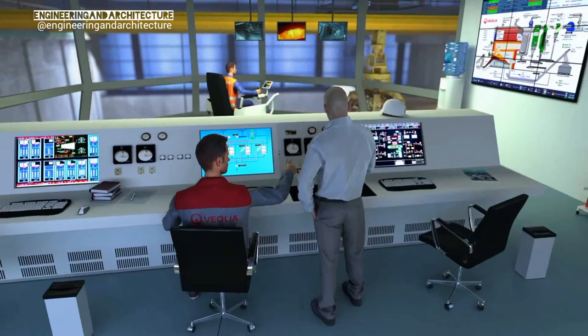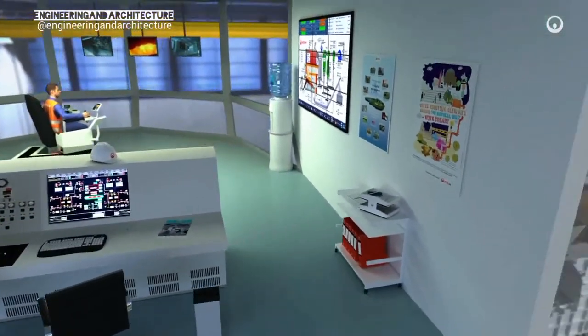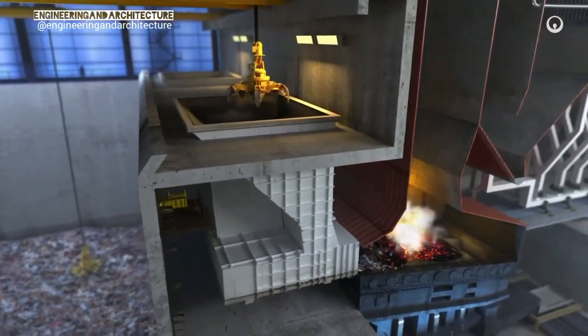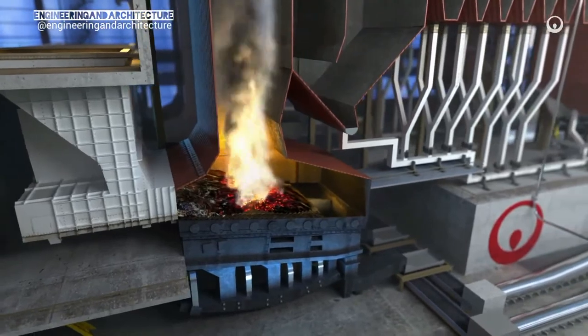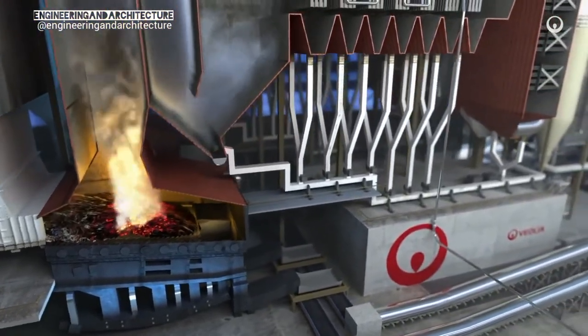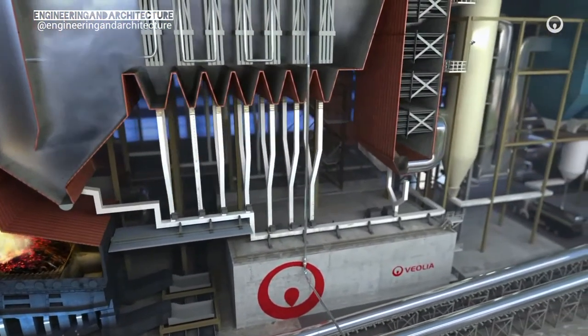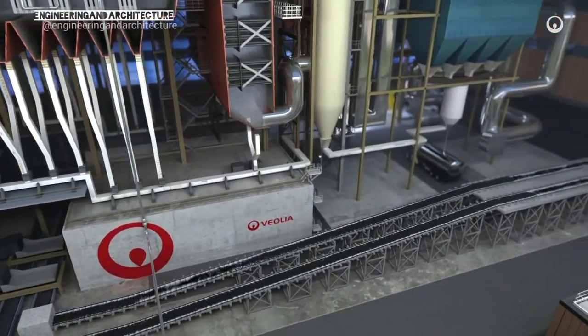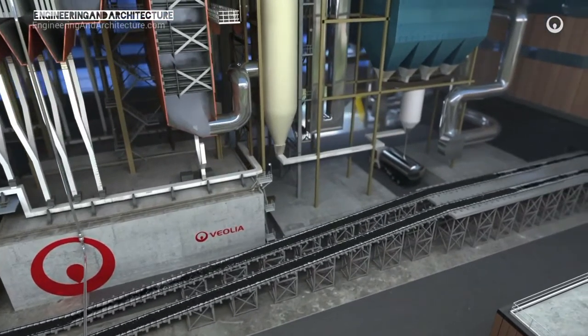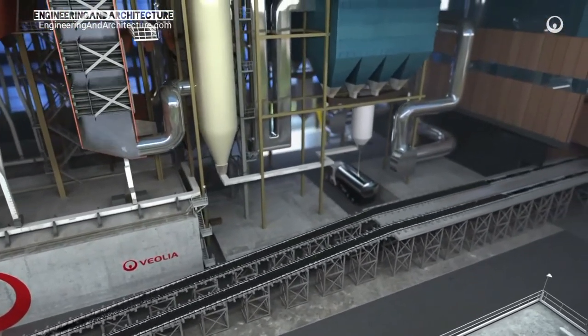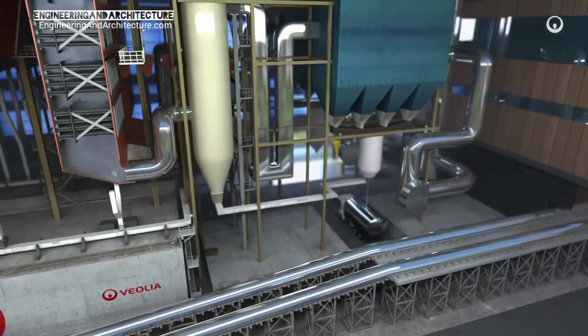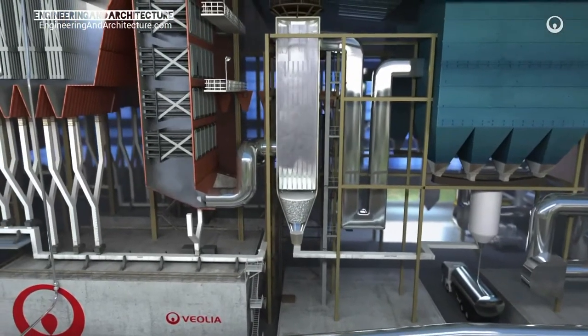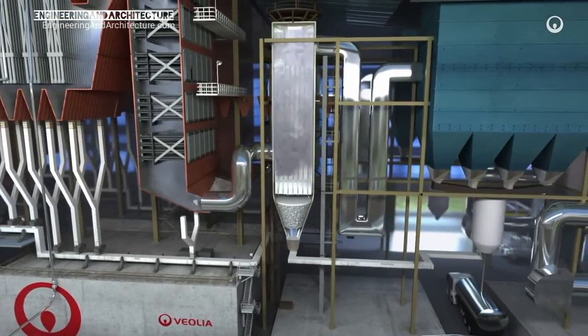In the control room, technicians control the facility's operation and the quality of the atmospheric discharge. The waste is tipped into hoppers to supply the furnaces and burnt at very high temperature. The plant is maintained under negative pressure to prevent any odors or off-gas from escaping. The clinker — the solid residue from incineration — is removed by a conveyor belt, stored, and will be recycled as earth-moving material for sub-base roads.